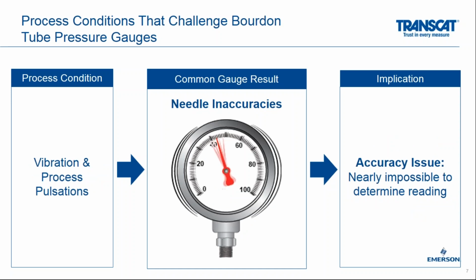Another one that's incredibly common is vibration or process pulsation. These are happening from 2 different things. Vibration just means the actual pipe and gauge are vibrating. Pulsation has to do with the actual fluid or gas in a pipe or tank pulsating. But regardless, what ends up happening is you get a lot of needle inaccuracies. And this is caused because the needle is bouncing around.